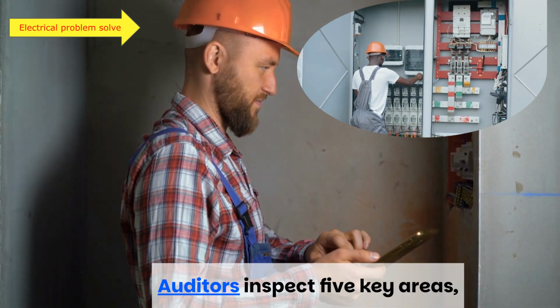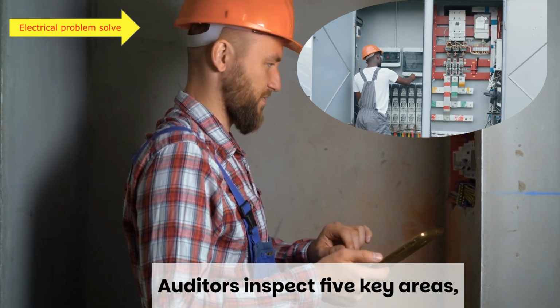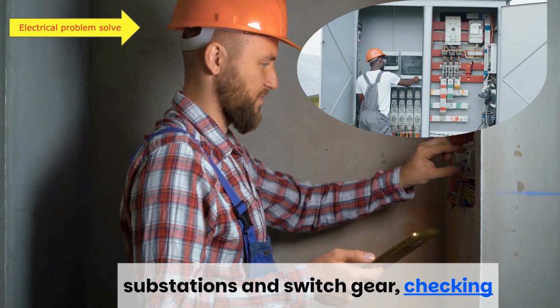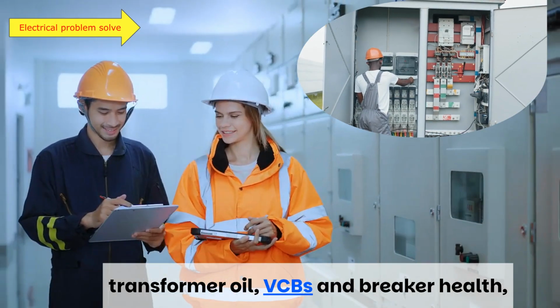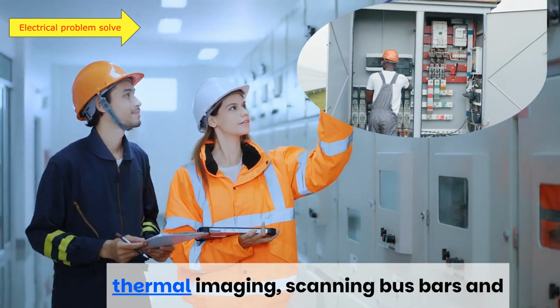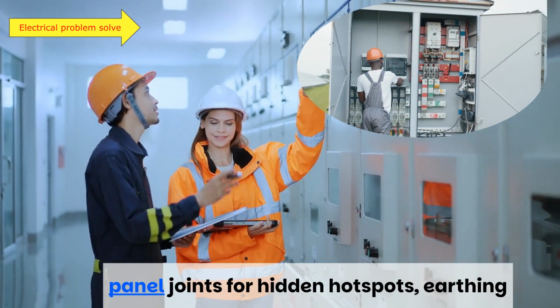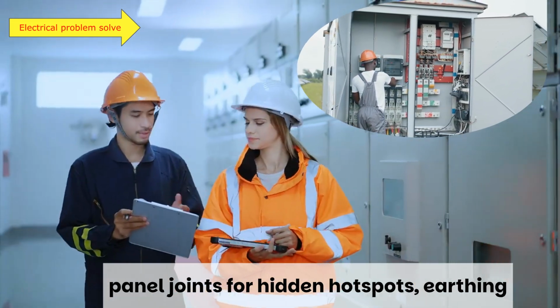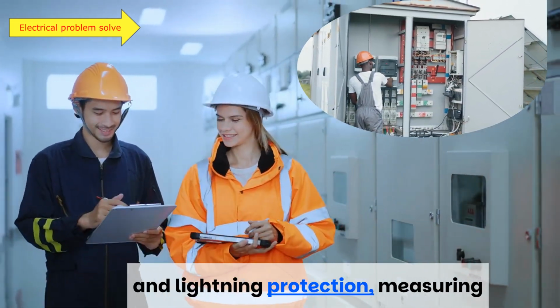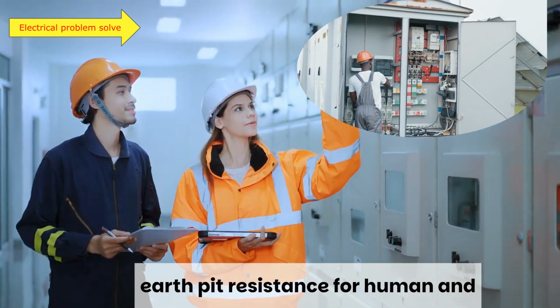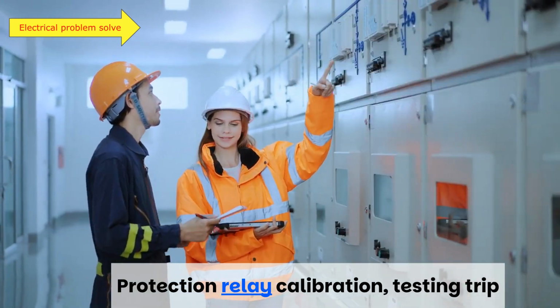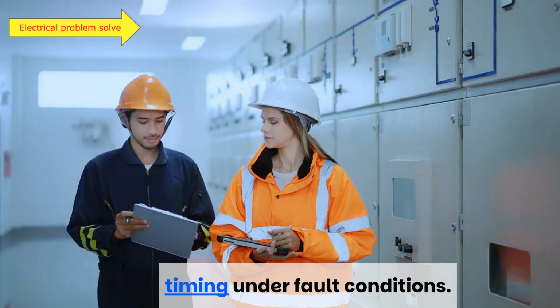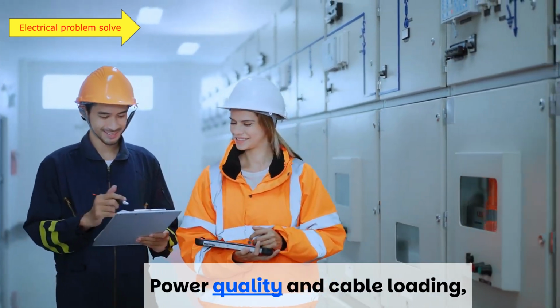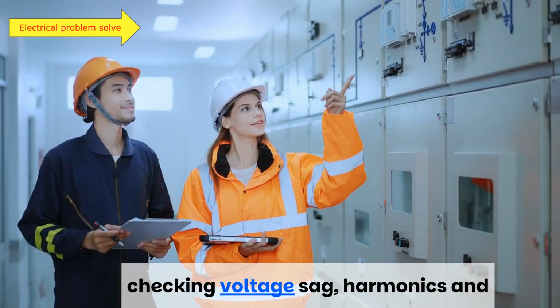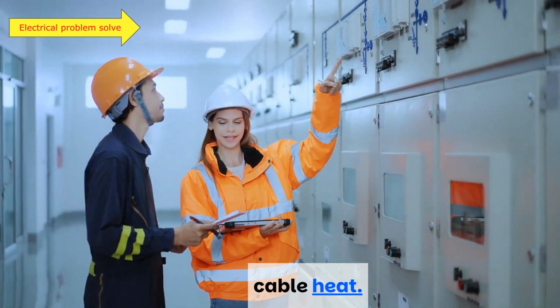Auditors inspect 5 key areas: substations and switchgear, checking transformer oil, VCBs, and breaker health; thermal imaging, scanning busbars and panel joints for hidden hotspots; earthing and lightning protection, measuring earth pit resistance for human safety; protection relay calibration, testing trip timing under fault conditions; and power quality and cable loading, checking voltage sag, harmonics, and cable heat.